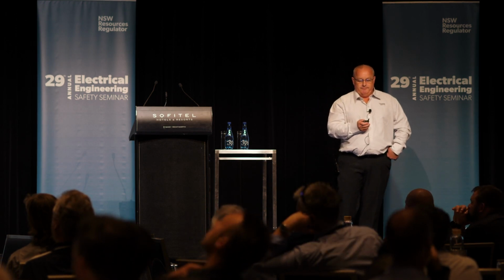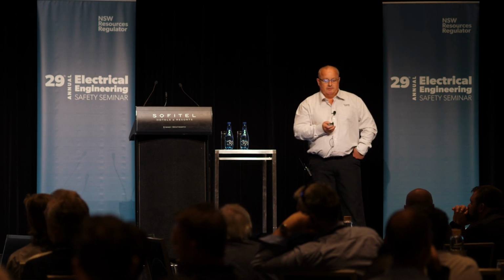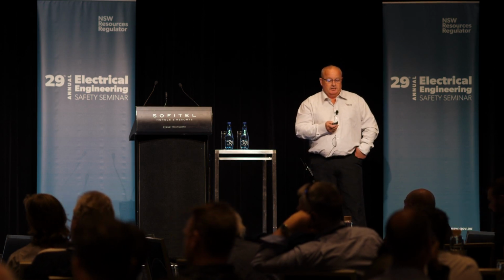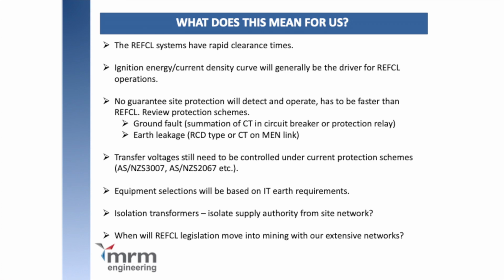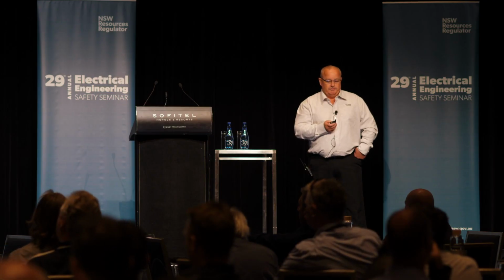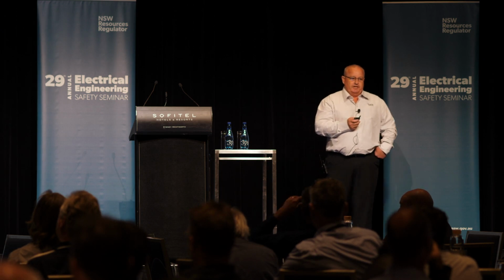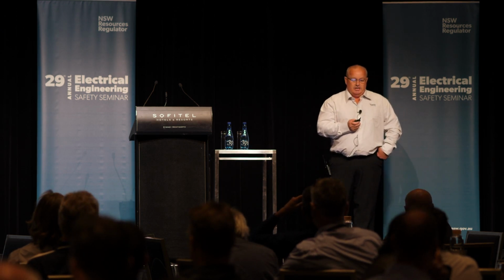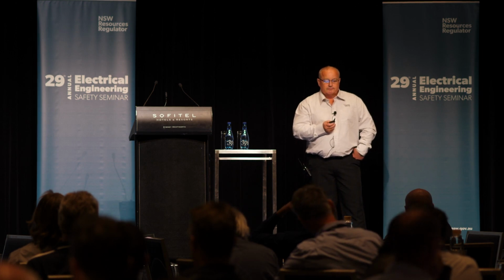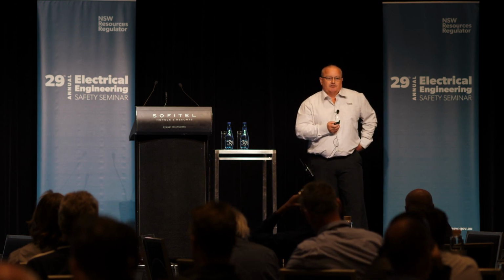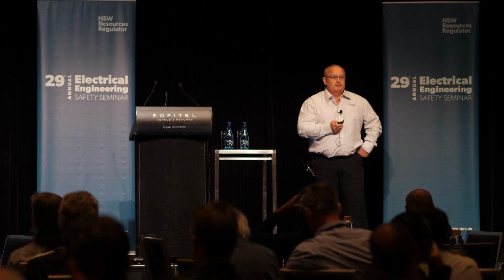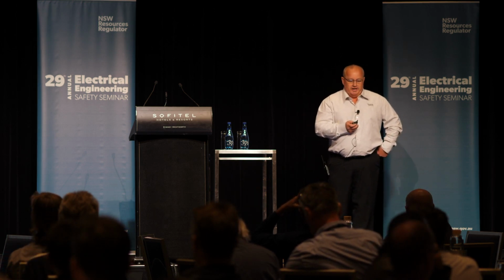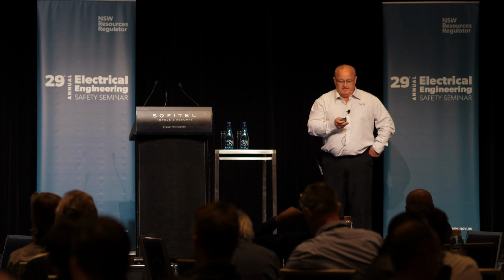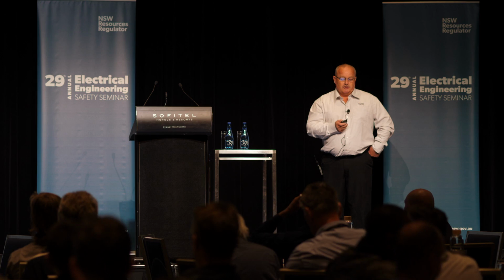So I guess what does that mean for us? REFCL has rapid clearance times. The bigger driver of all this is going to be the ignition energy. So you can look at the curves, look at the clearance times. Potentially we can't respond on the downstream side to any of the faults. I've actually spoken to one of their experts in Melbourne for the REFCL and asked him about how we're going to coordinate protection from upstream to downstream. His answer was, we don't know. We haven't installed one yet. We'll work it out when we get there. So it doesn't sort of provide a lot of guidance on that point at the moment.